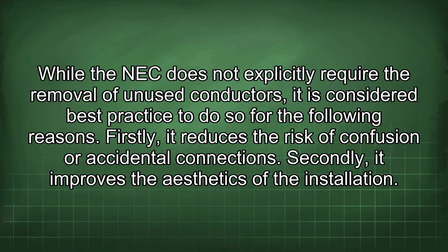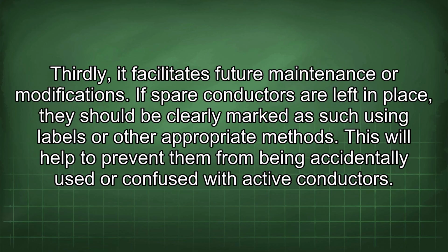While the NEC does not explicitly require the removal of unused conductors, it is considered best practice to do so for the following reasons. Firstly, it reduces the risk of confusion or accidental connections. Secondly, it improves the aesthetics of the installation. Thirdly, it facilitates future maintenance or modifications. If spare conductors are left in place, they should be clearly marked as such using labels or other appropriate methods. This will help to prevent them from being accidentally used or confused with active conductors.